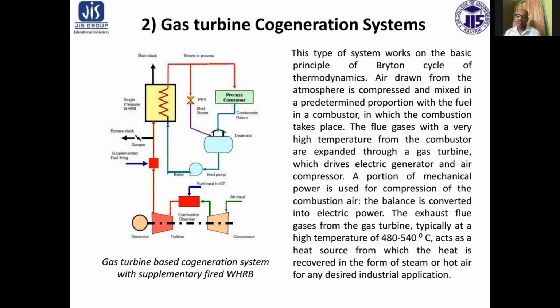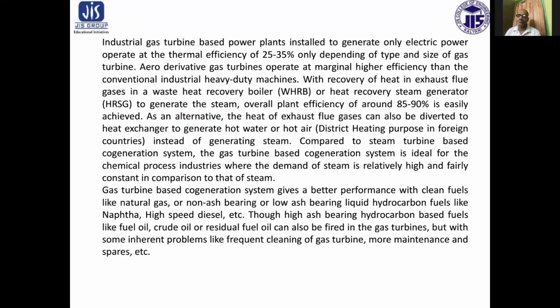The exhaust flue gases from the gas turbine, typically at high temperature, in the range of 480 to 540 degrees centigrade, act as a heat source from which heat is recovered in the form of steam or hot air for any desired industrial applications. Industrial gas turbine based power plants installed to generate only electric power operate at a thermal efficiency of only 25 to 35%, depending on the type and size of the gas turbine. Aeroderivative gas turbines operate at marginally higher efficiency than the conventional industrial heavy duty machine.